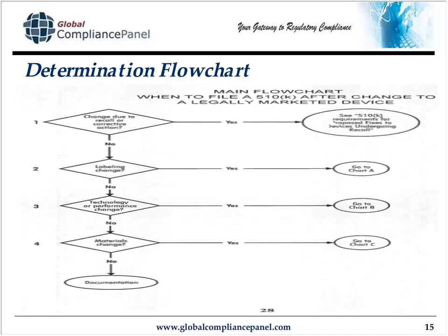I've copied some pages of the determination flow chart, which is when you need to submit a 510K. The cover shot here determines the origin of the change. Was the change due to a recall or corrective action? Well, if it was, you have to see a completely other guidance document that I'm merely pointing to during this presentation, but for most of the cases, most of the attendees, it's one of the other changes.